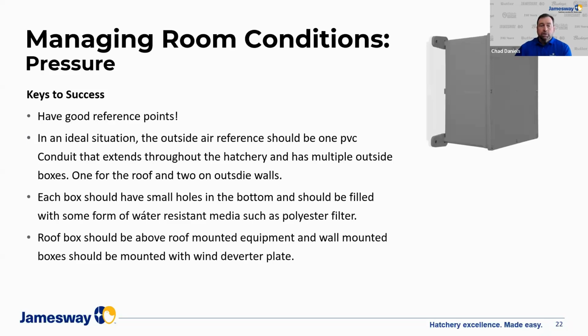In some cases, with the roof boxes, you want to make sure you get it high enough that the wind is not being diverted across the box because of a piece of roof mounted equipment. So it should be fairly high up on the roof. And then if it's wall mounted, like in this illustration, you should have what's referred to as a diverter plate. So if the wind comes across the ground and hits the side of the building, instead of shooting up into the bottom of this box, it should hit this plate. And that's going to divert the wind from blowing directly into the bottom of that box.